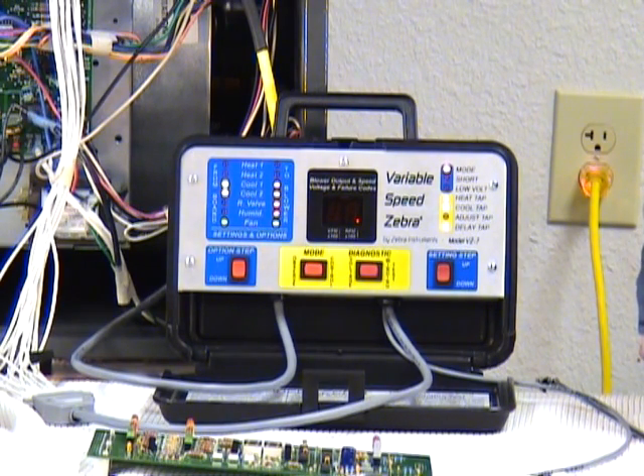Although the variable speed Zebra is designed to be used in a service environment, experience has shown our service department 2 areas where tool failure has often occurred. The first one is when somebody modified an input connector and they've introduced voltages higher than the VZ-7 was designed to withstand, i.e. higher than 24 volts. The second area, the biggest area where problems have occurred, is when appropriate care was not taken when plugging in connectors.